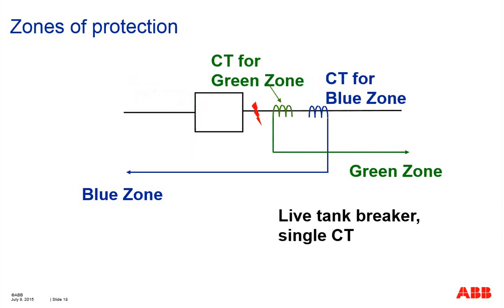In some unideal situations, you may not have the overlapping CT on this side of the breaker. Typically this would not happen very often for switchgear type bus bars. You see this a lot, for example, for a breaker-and-a-half type live tank CT.